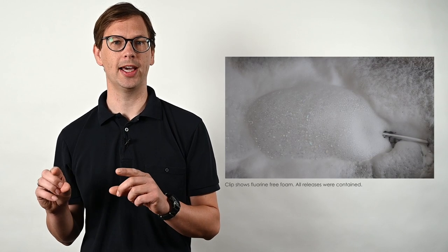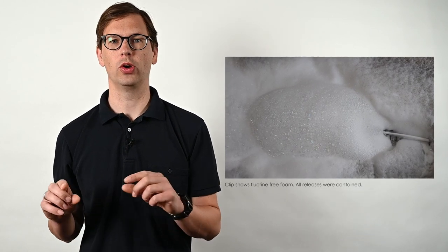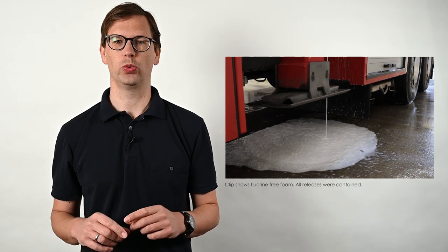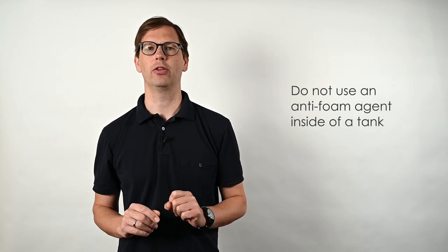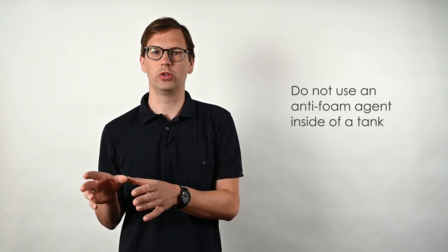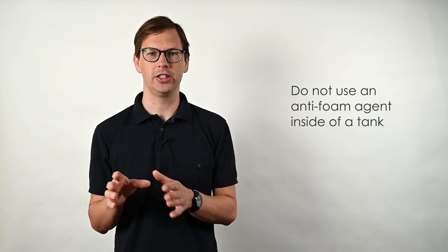You probably cannot fill up the tank to the top because you will get a lot of foaming, and the foam would overflow and contaminate equipment outside of the tank, and you don't want that to happen. By the way, do not use an anti-foam agent inside of the tank. It would help to destroy the foam, of course, but I'm not sure if this could destroy the new foam concentrate that you'd like to fill in after cleaning. You could use defoamer for foam outside of the tank, but you want to avoid that anyway. And of course, anti-foam agent destroys the foam, but not the PFAS.